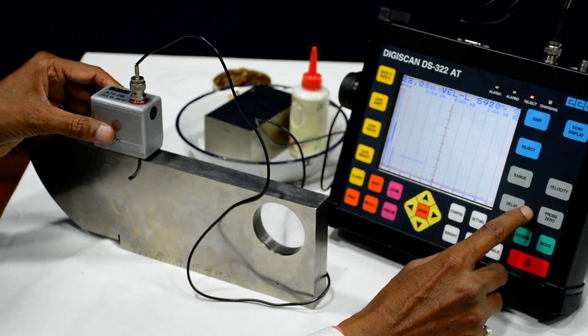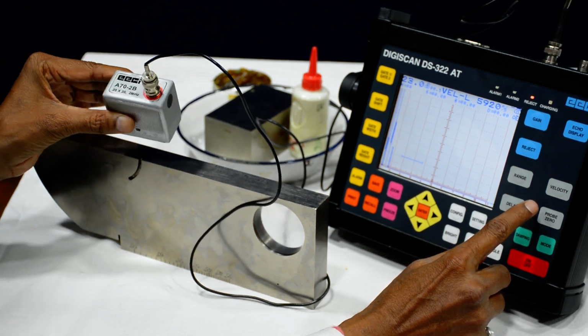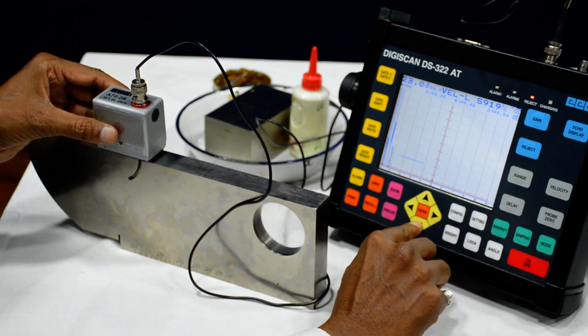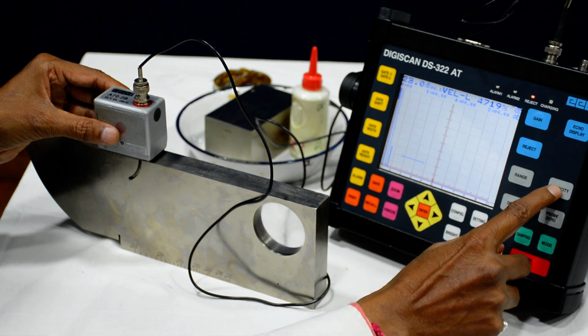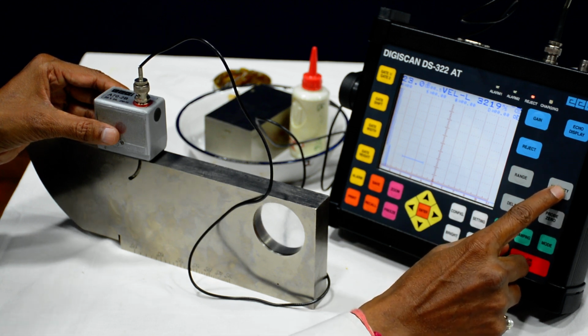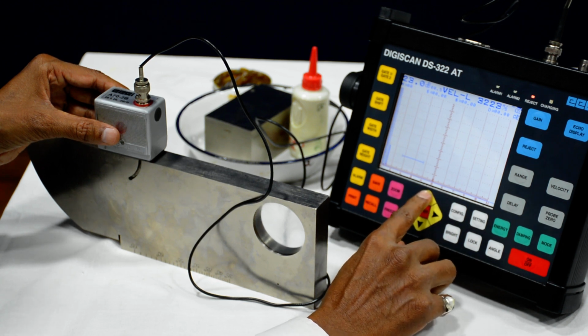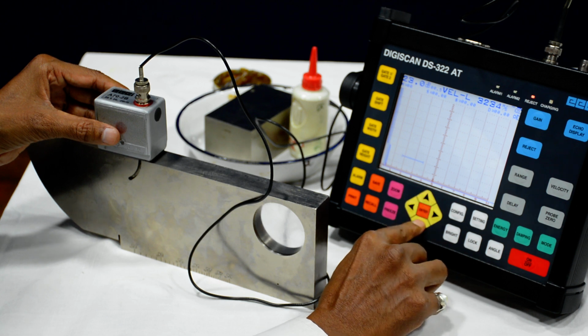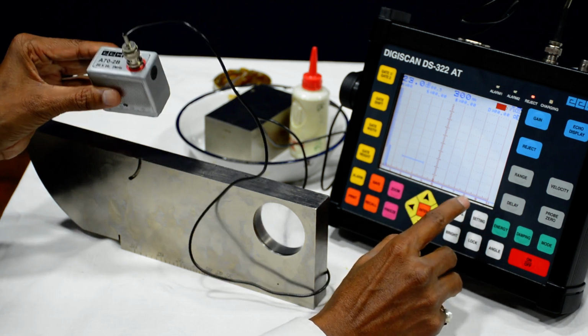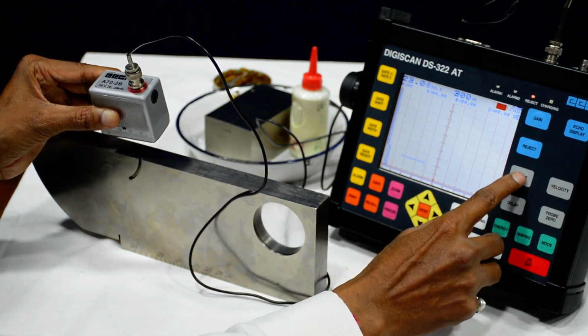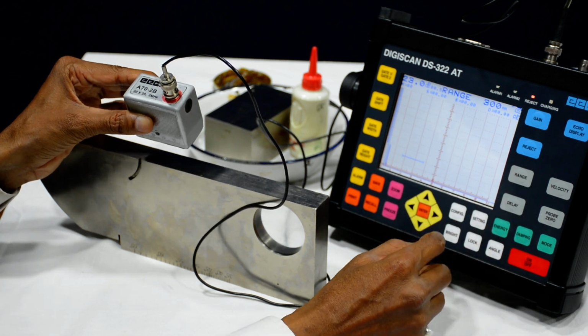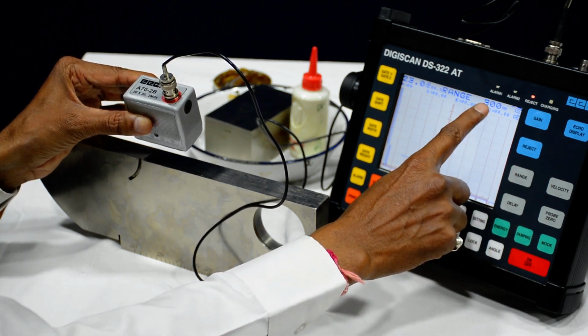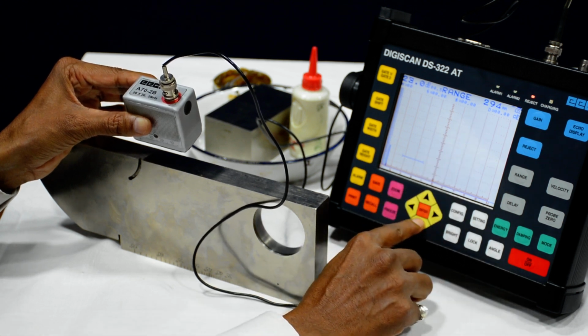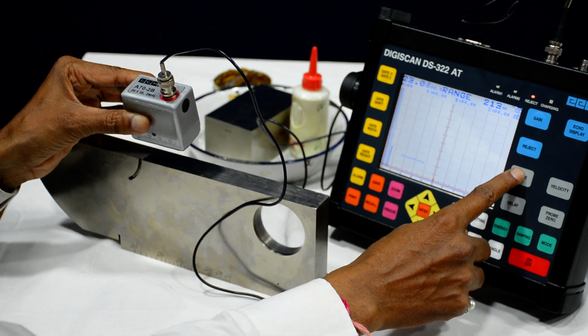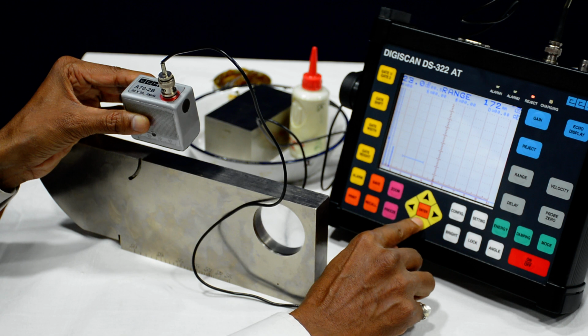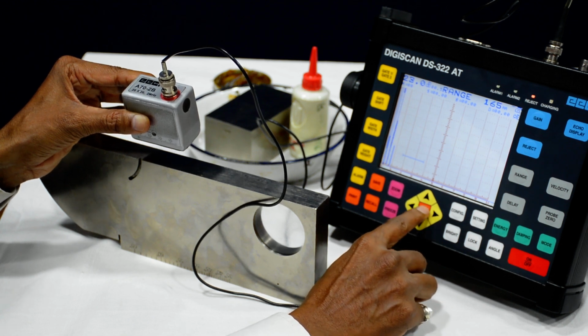Next, velocity. This is the angle probe. So for the angular probe, we have to make the velocity 3230. So we will change this to 3230. So now velocity is 3230. For this 70 degree, we have to take the range 165. Here range is 300. So we will make it 165. Again we will press here. So it will change cursor and now we will make it 165. Okay, now this is 165.